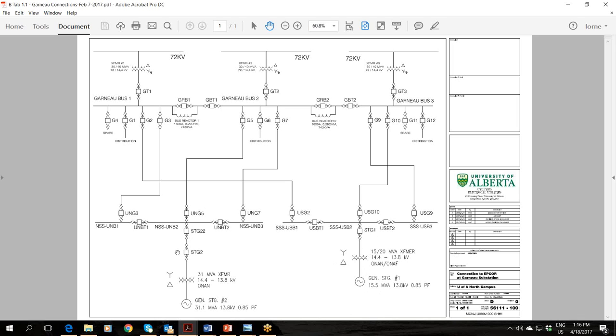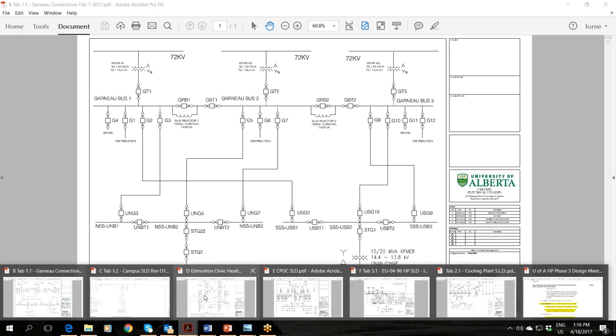Something that's kind of interesting to note, we got 2 breakers shown here, and that is accurate. The north switching station, again, is the north part of campus. The south switching station is pretty much attached to the heating plant. These 2 steam turbine generators are in the heating plant, so we ran almost 2 kilometers of cable to get from this breaker that's in the heating plant to this breaker, which is in the north switching station, just because this was the best point to put it in terms of the campus power system itself.